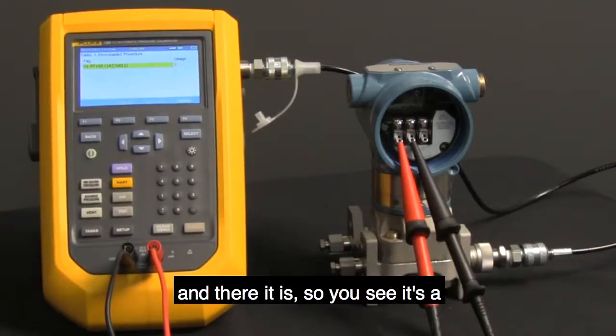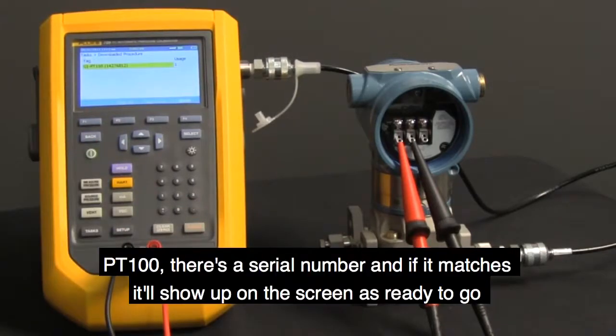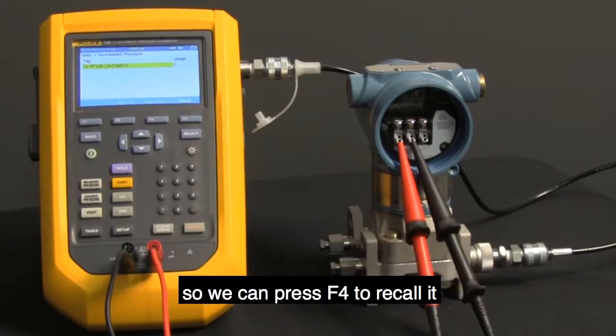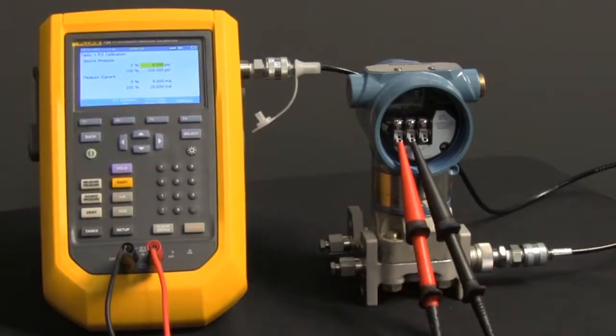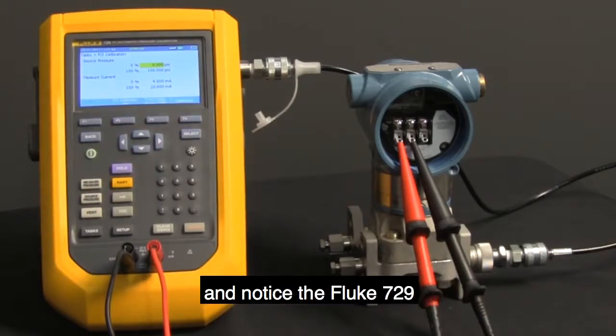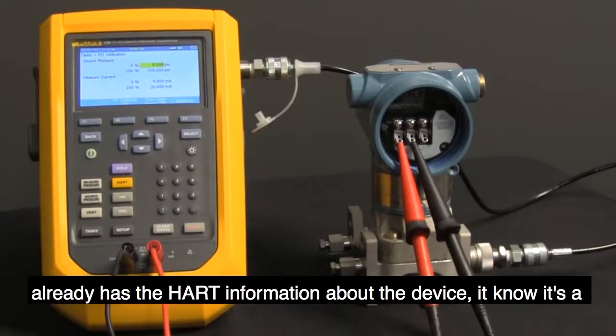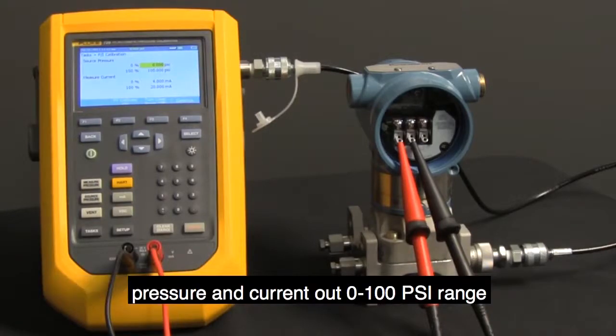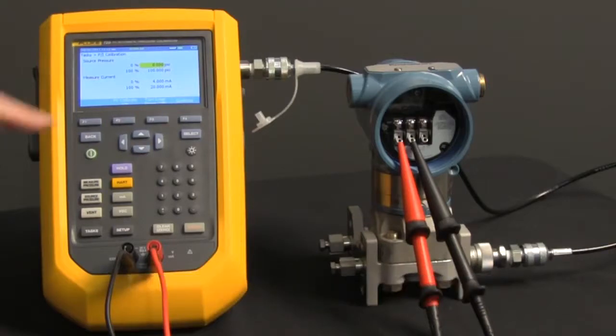So you see it's a PT100. There's a serial number, and if it matches up it'll show up on the screen, ready to go. So we can press F4 to recall it. And notice the Fluke 729 already has the HART information about the device. It knows it's a pressure in current out, zero to 100 psi range. Press continue.